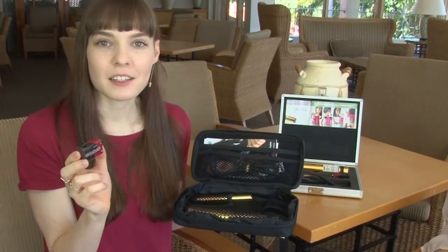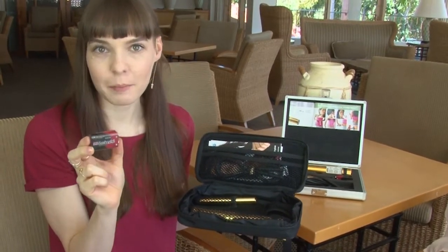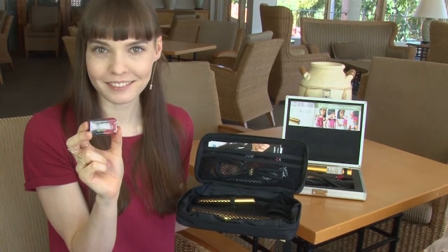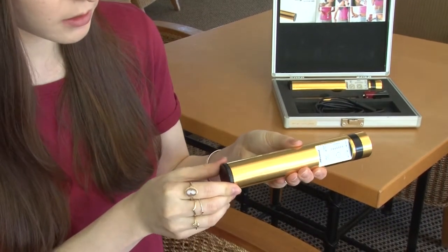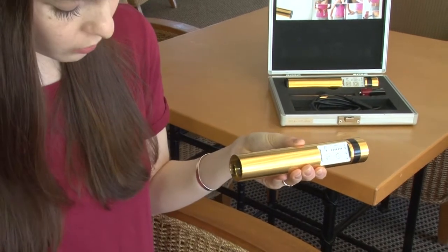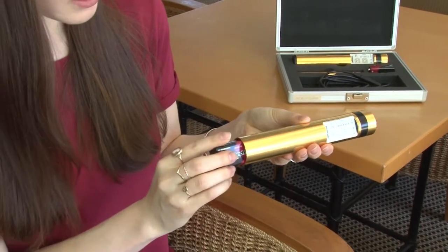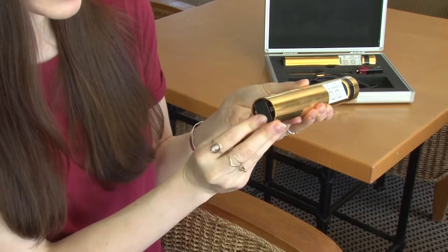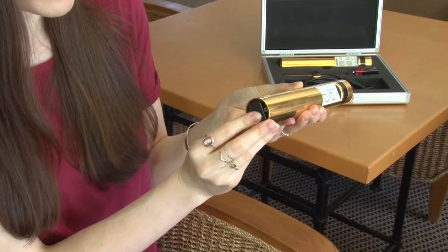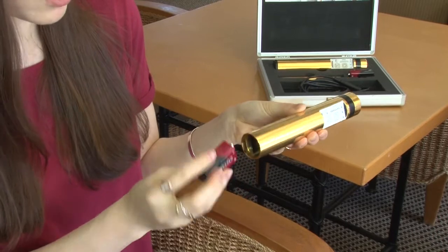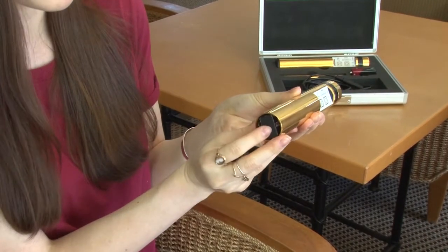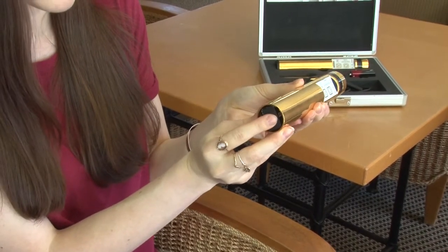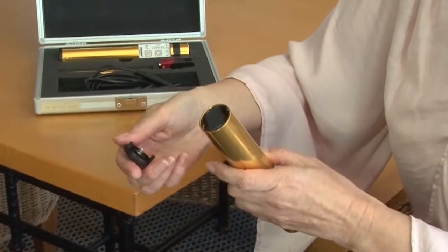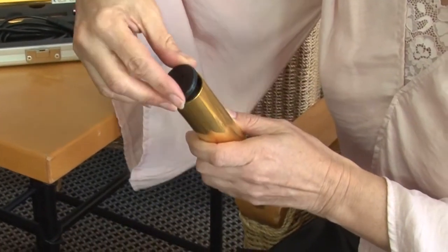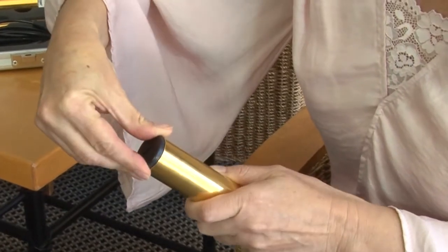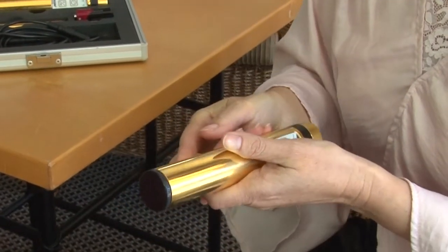When setting up your device, it's really important to remember the first step is taking the plastic off the battery. Take your PowerTube out of the case, turn the cap in the direction of the arrow, take your battery and place it inside the PowerTube. If the battery is not inserted correctly, there will be no movement. Take your battery out and try again. Once the battery is inserted correctly, there will be a slight bounce. Then take the cap, align the grooves, push down with the spring in the middle and twist to close.